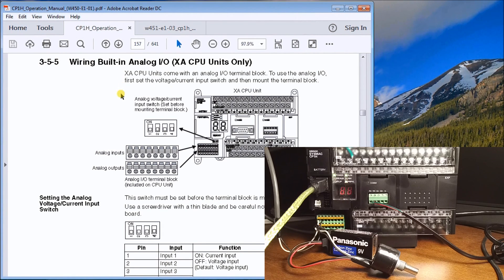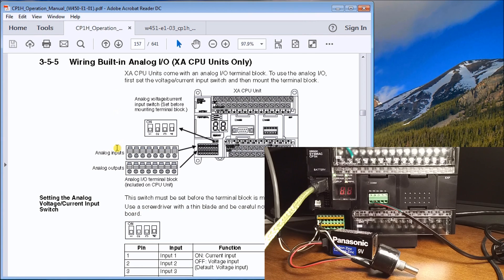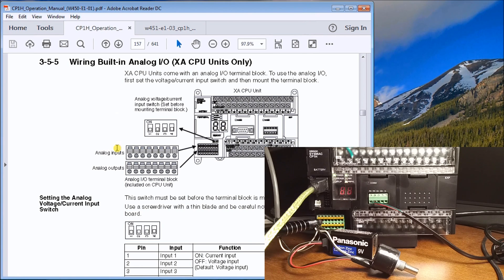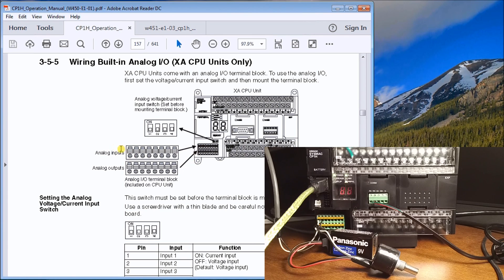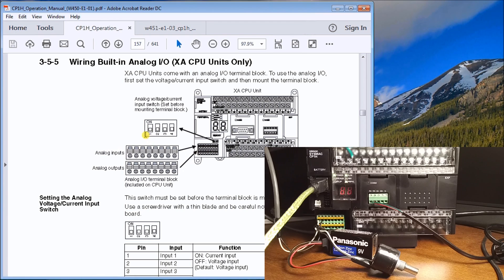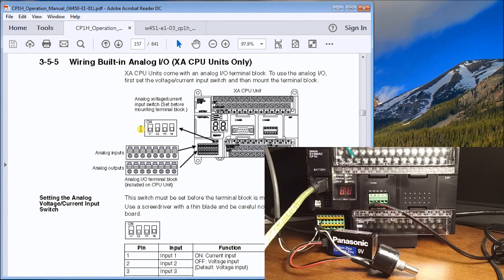From the PLC wiring diagram itself, you'll see that we have built-in connectors right down here. We're using the first one in the top row—the first one's my positive, next one's my negative. Inside there's a small area where we can switch between current or voltage.